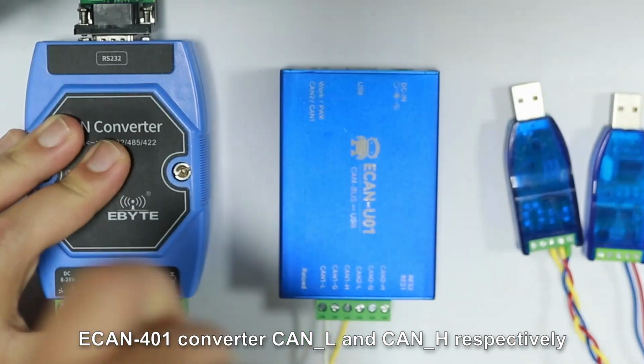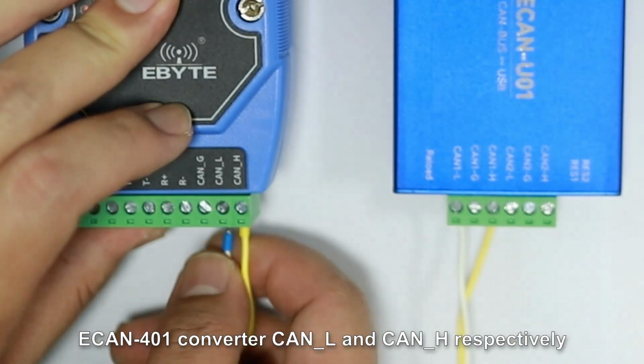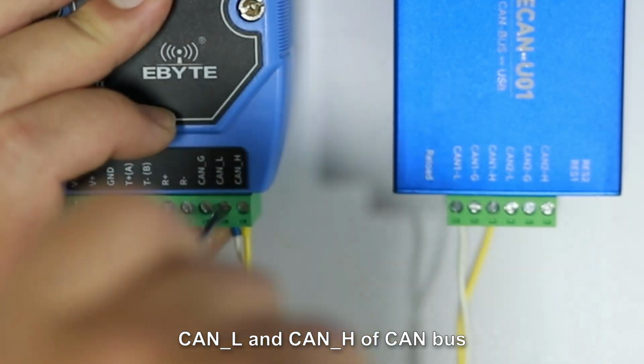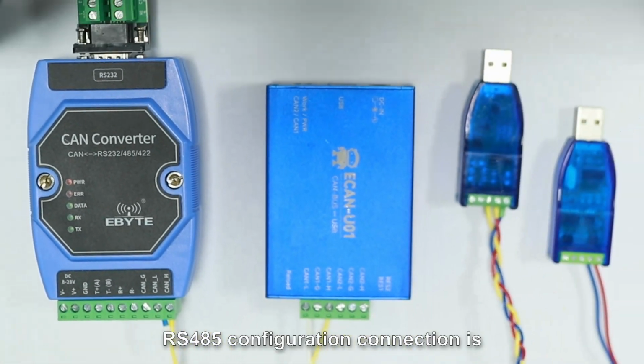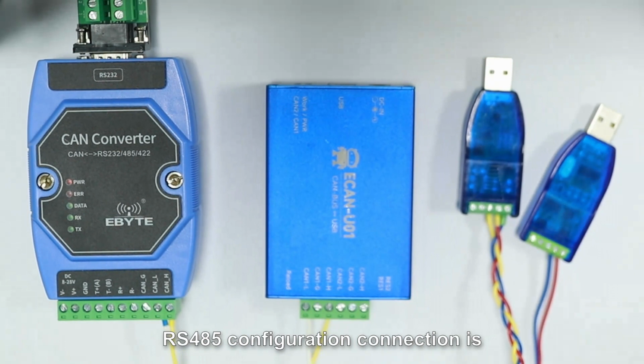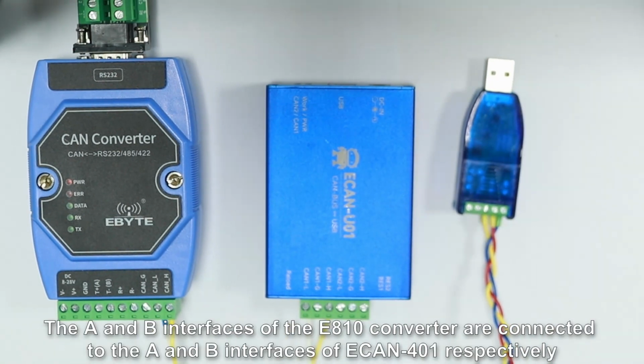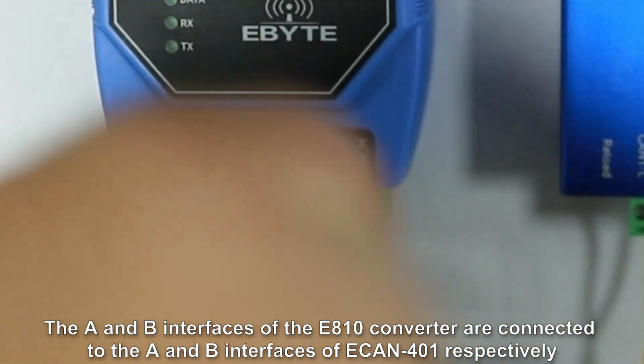Physical connections. Connect the ECAN-401 converter CAN_L and CAN_H respectively to the CAN_L and CAN_H of the CAN bus. The RS485 configuration connection is: the A and B interfaces of the E810 converter are connected to the A and B interfaces of ECAN-401 respectively.